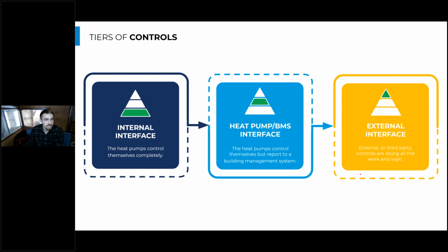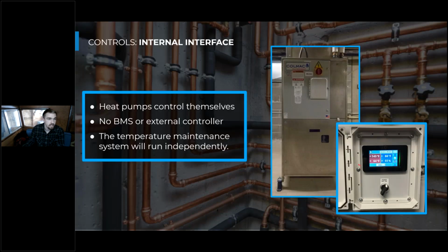And so a little more detail on the internal interface. I mentioned the heat pumps control themselves completely, so there's nothing external to the heat pump that's telling it what to do. I should say there's nothing intelligent telling it what to do, because these heat pumps will oftentimes be supplied with their own temperature sensors that will run to the storage tanks.